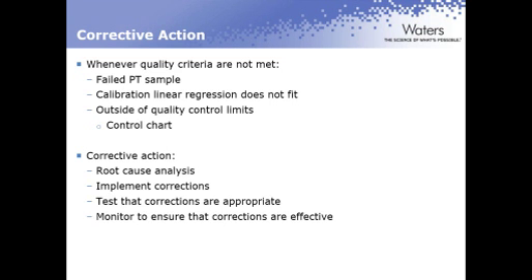So after we've implemented those corrections, we don't really know if those corrections fix the problem or not. How are we going to do that? We need to test to make sure that those corrections are appropriate. What can we use to test that? CRMs. Because again, you've got a value certified by someone else, so you know what the value is supposed to be. You know what the acceptable limits are supposed to be. Okay? So you can either run a CRM with a known concentration, or use a proficiency test, or PT, so that you don't know the value and you can truly test whether the corrections that you implemented work.